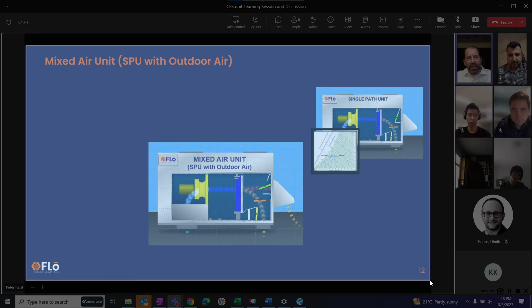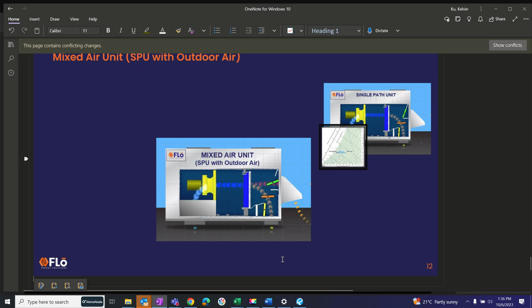What we need to do, and what the industry often does, is bring some outside air into these units. We call this a mixed air unit—a single path with outside air. You might call them RTUs, rooftop units, but that's not really the right technical name, since everything on the rooftop is a rooftop unit. So we kind of call these mixed air units.